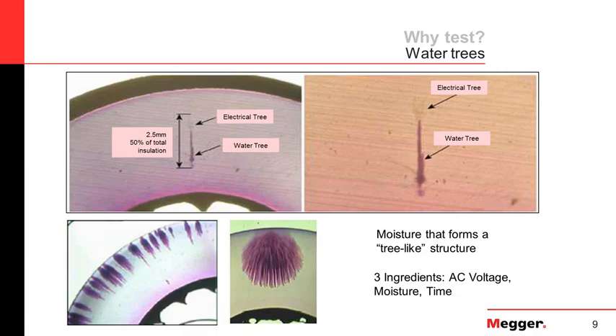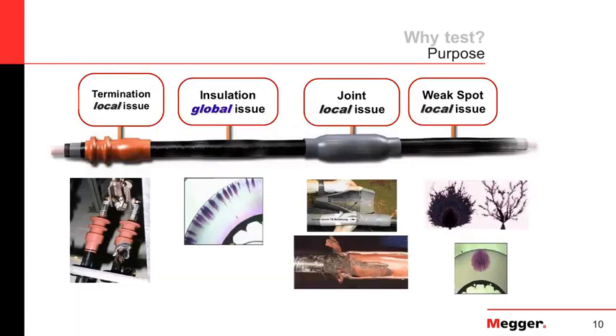You can have water trees all over your cable — coming from the conductor or from the semiconductor. Only one of these needs to convert to something called an electrical tree, which is a carbonized path, to create a cable failure. Because water trees can occur all over your cable, this is considered a global issue. You also have more localized issues, like a bad joint, a bad termination, or a localized weak spot such as an insulation dig-in.